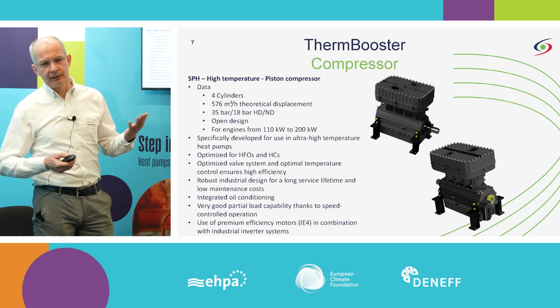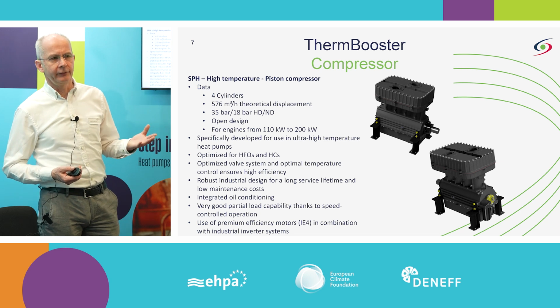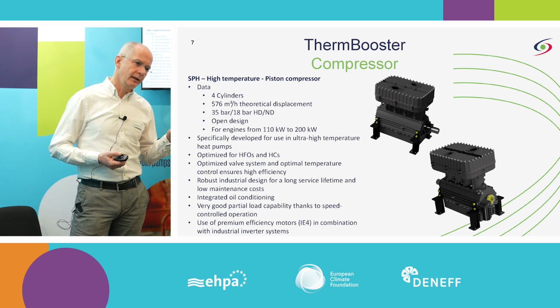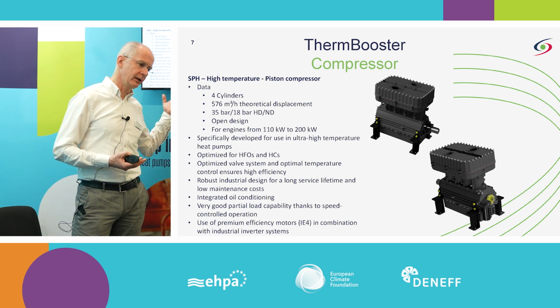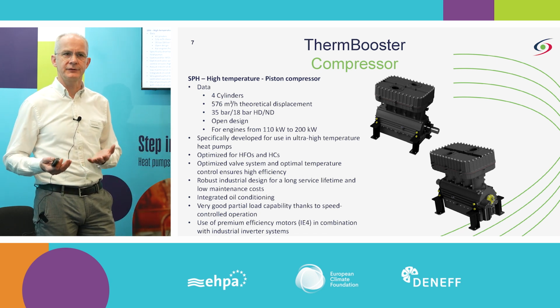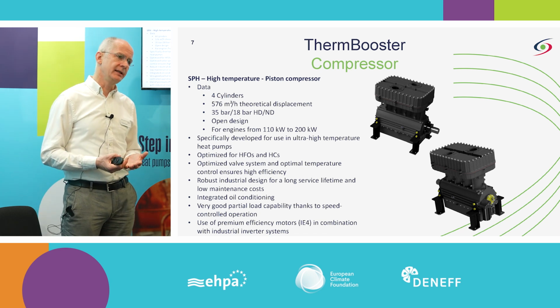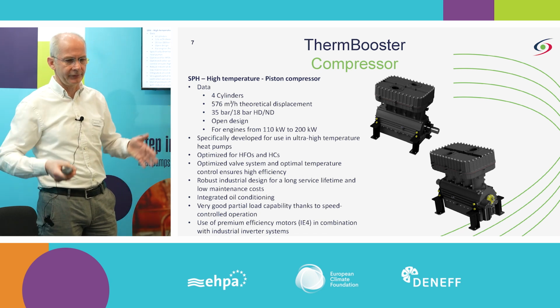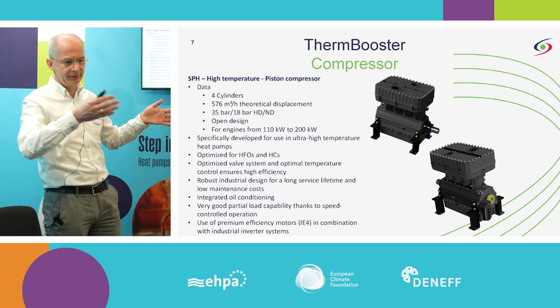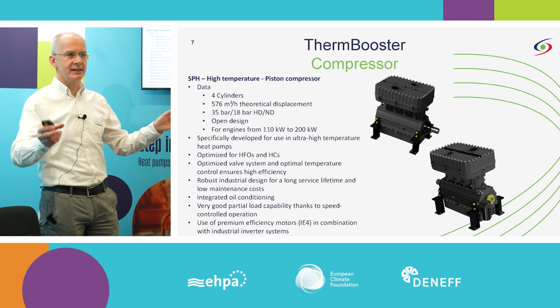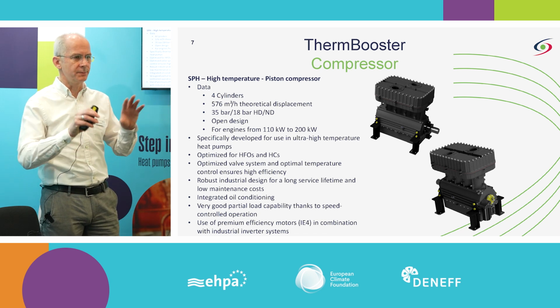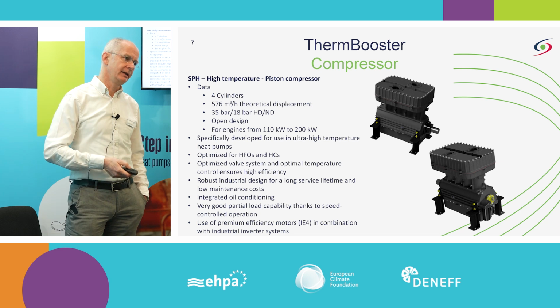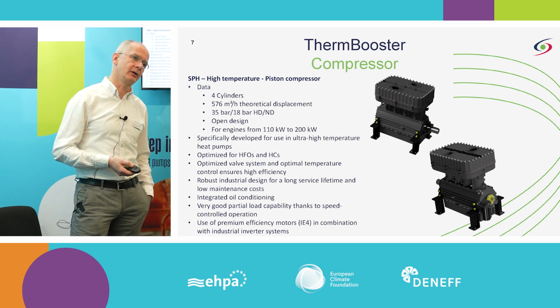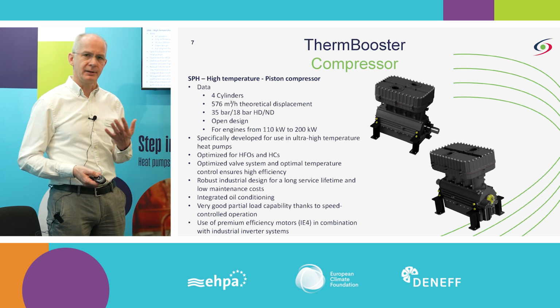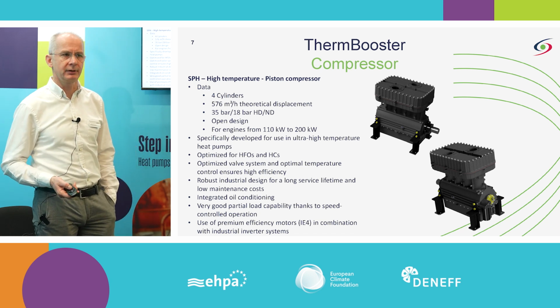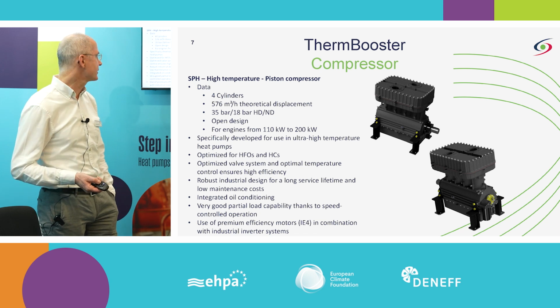Due to the fact that we are using frequency controlled electrical motors, and we are having a piston compressor, the part load capability of the unit is quite good. Means, let's say, over the widest range of the application. So we usually say that from 30% to 100% load, we can use the unit, and just at the outer edges, the efficiency drops a little bit, but in principle, it's really constant over the entire range of operation. Therefore, also part load operation is easily possible without any loss of efficiency.